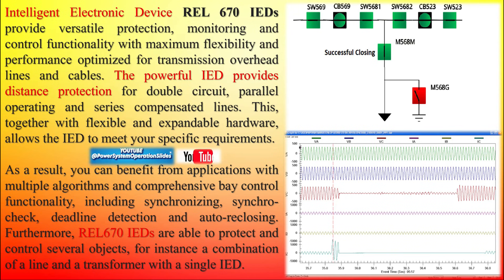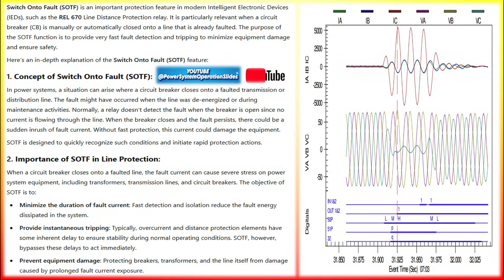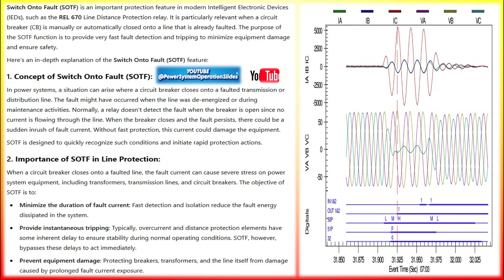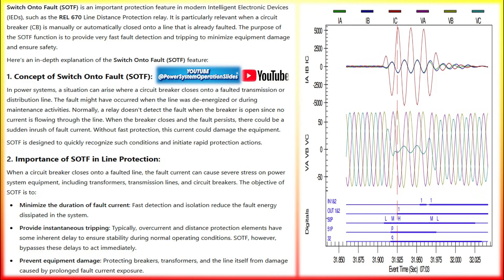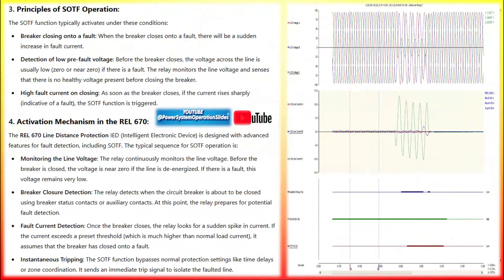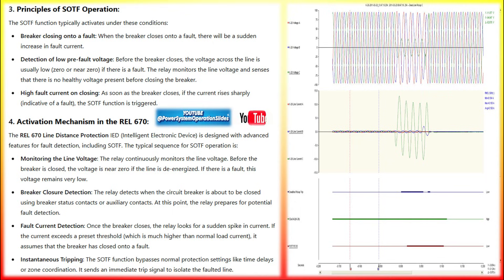In power systems, a situation can arise where a circuit breaker closes onto a faulted transmission or distribution line. The fault might have occurred when the line was de-energized or during maintenance activities. Normally, a relay doesn't detect the fault when the breaker is open since no current is flowing through the line. When the breaker closes and the fault persists, there could be a sudden inrush of fault current. Without fast protection, this current could damage the equipment. SOTF is designed to quickly recognize such conditions and initiate rapid protection actions.